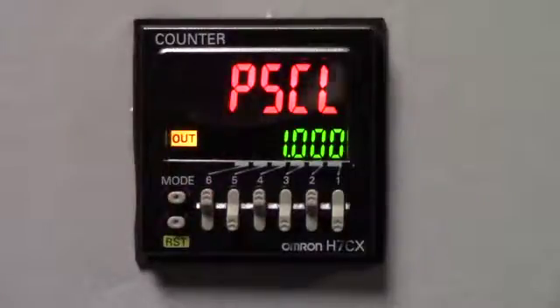Next is the pre-scale, PSCL. What's interesting about this function, it's a way of scaling the input to equal a certain amount of counts on the display. The typical application would be using an encoder needing to scale the display to read a number of feet or meters traveled. In this application, once again, since we don't have an encoder, we're just going to keep it with the factory default of a thousand.